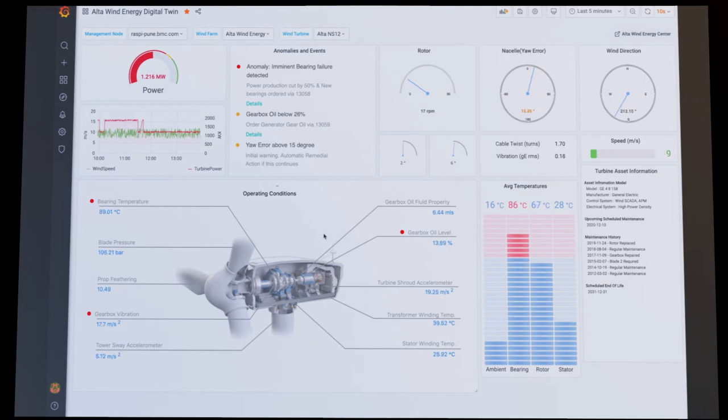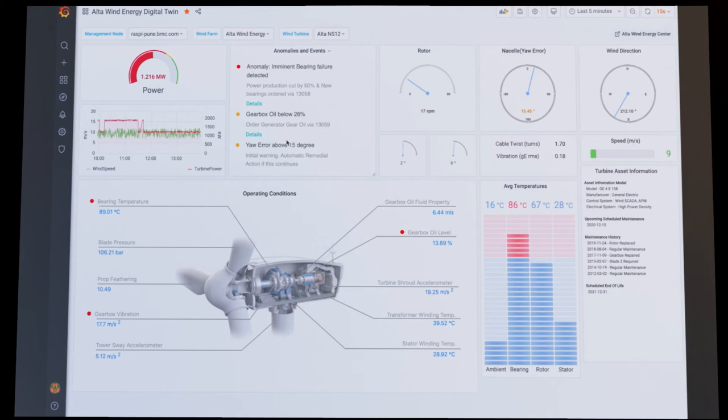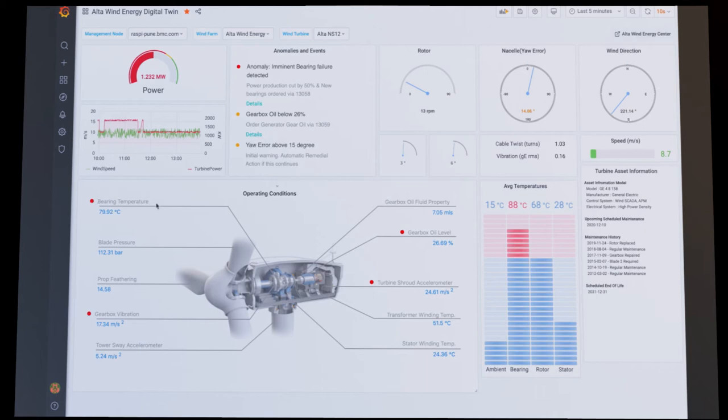As you can see, there are several conditions affecting the operation of this turbine. In the anomalies and events dashboard, we can see critical events that have occurred and remediation action taken. Sensors have detected low oil in the gearbox. This, in turn, has led to an increase in bearing temperature and gearbox vibration.